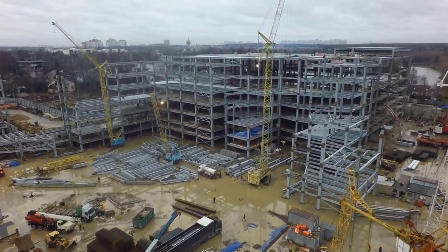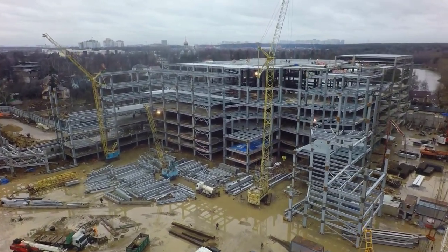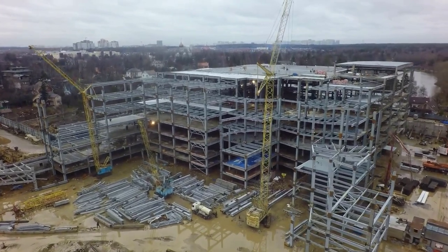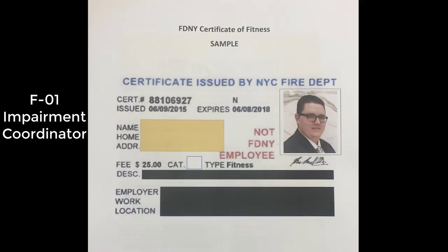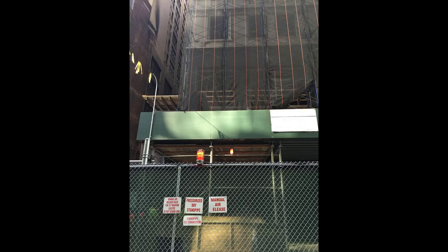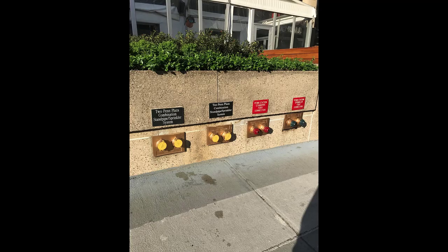When you have an impairment of the fire protection system, you will need to designate an impairment coordinator. This person must hold a valid F01 license with the fire department. There are two types of impairments: planned and unplanned. There are also two types of discs: a red disc when the entire system is fully impaired, or a partial impairment, and you will use a yellow disc.